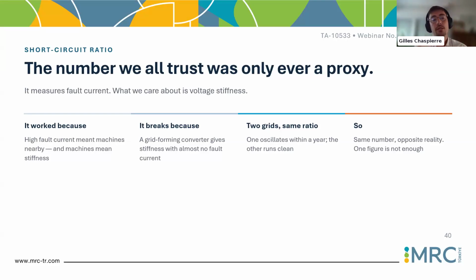So if you keep using the short circuit ratio in a power system that is evolving very fast, you will be misleading. At the early stage of a project, you might spot very weak areas of your system which are wrong, because you have completely neglected the presence of grid forming assets. And at the operational stage, a low short circuit ratio tells you, okay, you need to run dynamic simulation to verify this result. So you will run dynamic simulation all the time, because the short circuit ratio will be very, very, very pessimistic, and you will lose a lot of time.